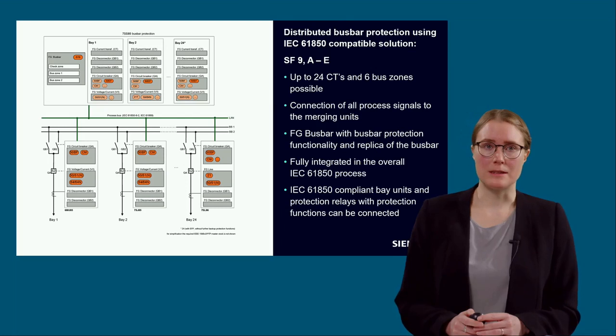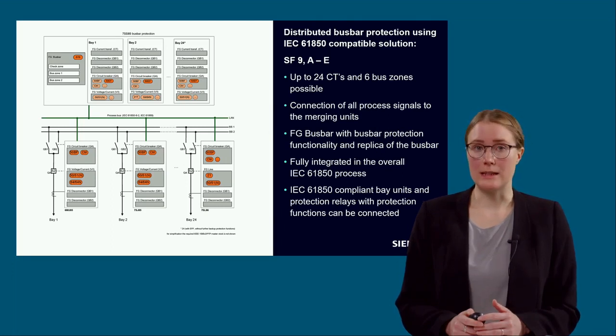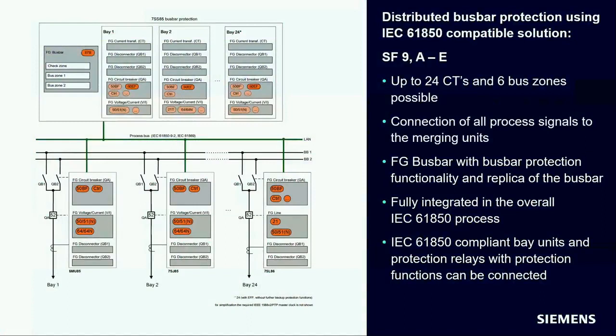In a distributed system, it is also necessary to parameterize the merging unit. Just like for the base in the 7SS85, we need the same function groups. About the bay-related functions like circuit breaker failure protection, end fault protection, or backup overcurrent protection, some of them can be configured in the merging units, some of them in the central unit. In this example, the end fault protection function is configured in the 7SS85 bay in the function group circuit breaker. For end fault protection, this is the only possible solution.